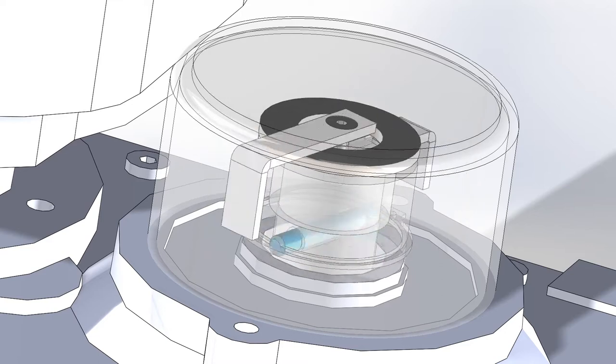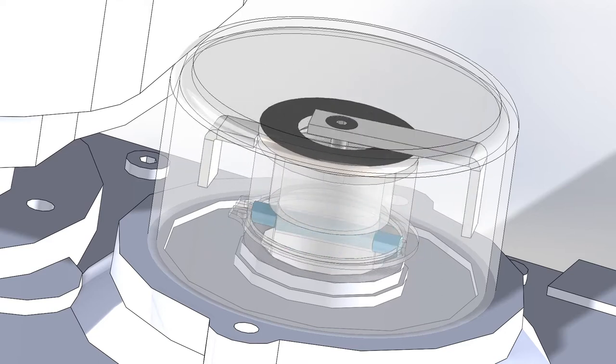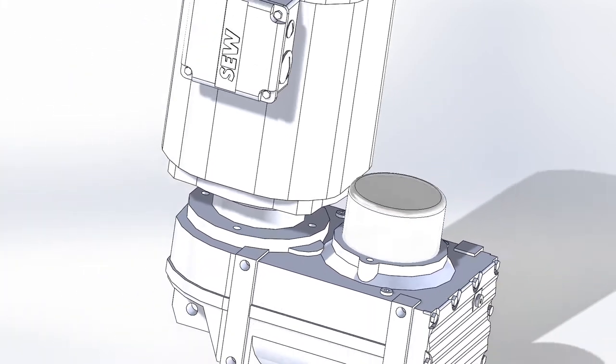If the drive experiences torque levels greater than the rated value, the shear pin is designed to break, preventing further damage to the rest of the unit. If this occurs, the shear pin will need to be replaced before the drive unit can be operated.